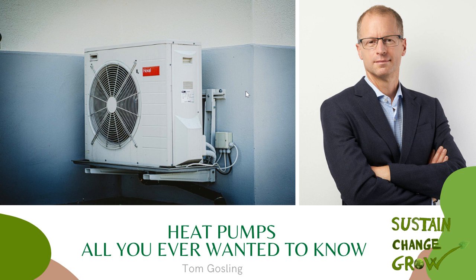And then there's one more policy implication, which is that at the moment, the government has this very binary view around heat pumps. So you only get the 7,500 subsidy if you rip out your gas boiler, completely dispense with it, and do all of your heating through a heat pump. Now, the problem with that is you then need to design your entire system to cope with those few really cold days in the year when the heat pump is operating at a lower flow temperature, lower water temperature. So what that means is that you generally have to have bigger radiators, a bigger heat pump, and so on and so forth, in order to cope with that really small number of days.